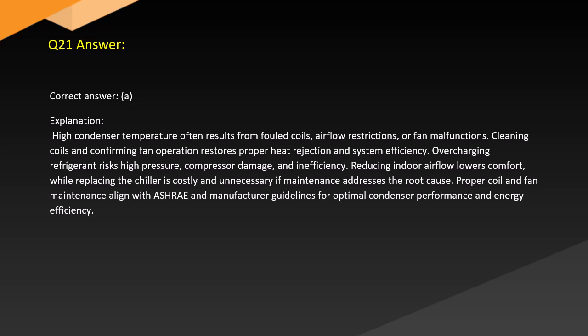Answer. Correct answer: A. Explanation. High condenser temperature often results from fouled coils, airflow restrictions, or fan malfunctions. Cleaning coils and confirming fan operation restores proper heat rejection and system efficiency. Overcharging refrigerant risks high-pressure compressor damage and inefficiency. Reducing indoor airflow lowers comfort, while replacing the chiller is costly and unnecessary if maintenance addresses the root cause. Proper coil and fan maintenance align with ASHRAE and manufacturer guidelines for optimal condenser performance and energy efficiency.